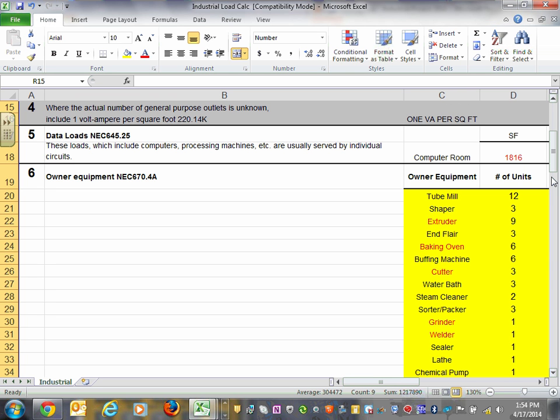The servers that they use in these data centers, right now, I believe it is 200 watts per square foot, but they're moving towards racks. So you have a rack going up, and the rack, I think, is 5 kW. So they allocate every rack you want to put in, and a rack is, what is it, 2 feet by 2 feet, give or take, to maybe 3 feet by 3 feet, and going all the way up to 8 foot, maybe 7 feet, something like this. And you fill them with servers based on the specification.